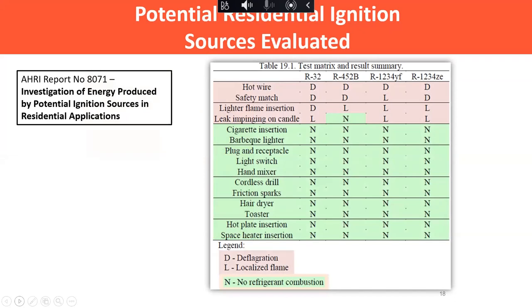This is again talking about ignition sources, and we talked about minimum ignition energy. This was a report AHRI did a couple of years ago, looking at potential things - can these common items that may be around where you're going to be working serve as an ignition source? This isn't definitive, but it certainly gives you a good sense of things like light switches or hair dryers, toasters, even a barbecue sparker igniter do not have enough energy to ignite an A2L.